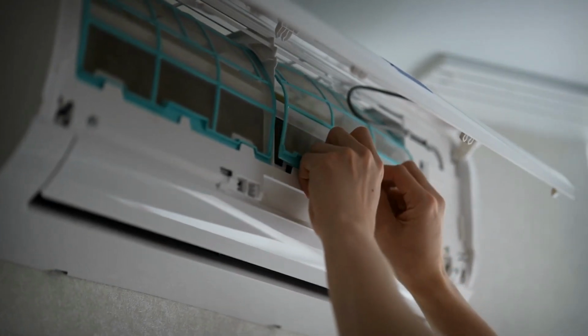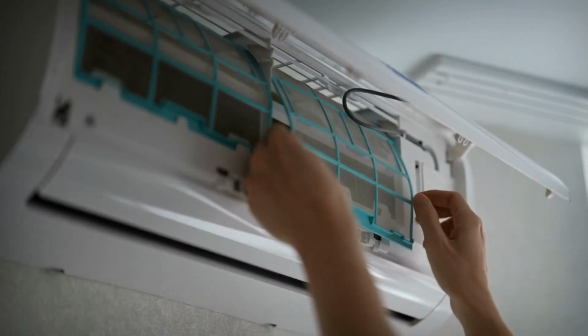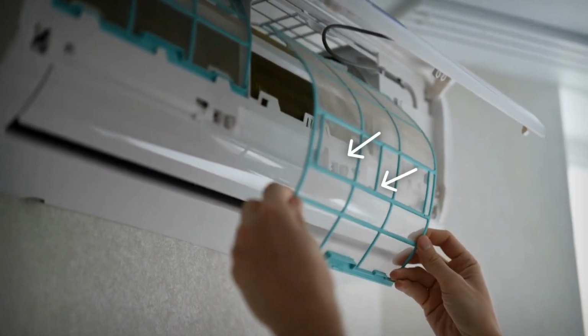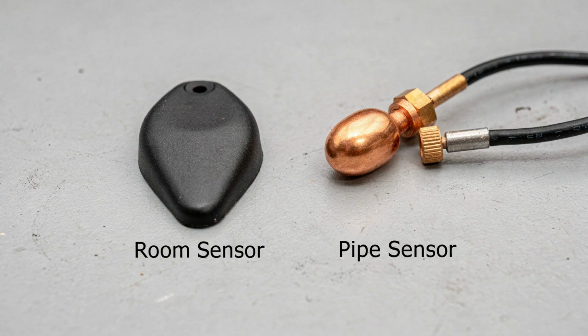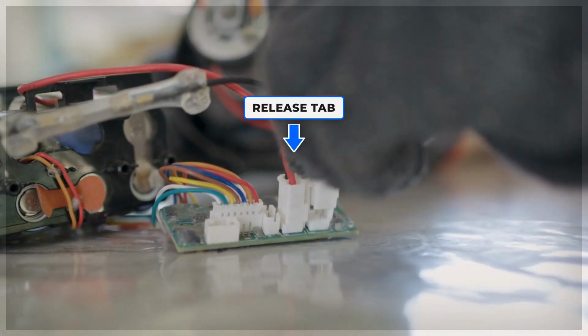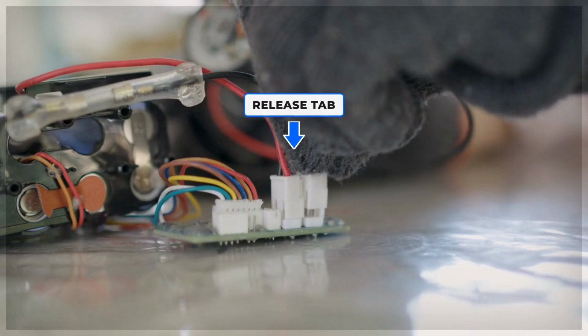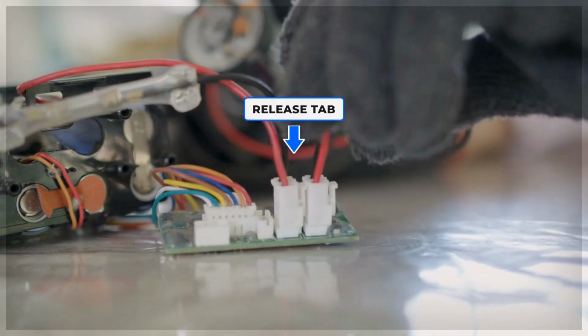Let's locate this sensor on the unit by opening the front panel. Slide out the dust filters. Right in front of the evaporator fins, you'll see two wires leading to a small black plastic teardrop bulb. Do not confuse this with the copper pipe sensor. The room temperature sensor is usually a black epoxy bulb suspended in front of the fins. Follow that wire back to the control board. Unplug the white 2-pin connector carefully by pressing the release tab, never yank the wires.